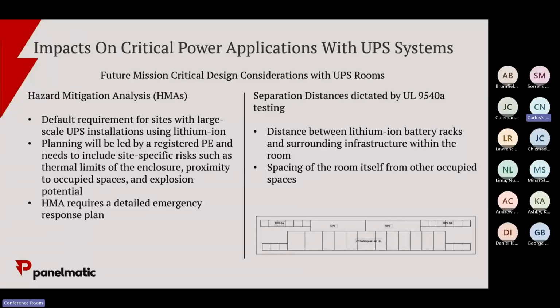The battery manufacturer will probably say you voided our warranty. A lot of the 3 foot spacing from the back is to move it away from the doors in case you have to open them, but it's also against that firewall and against anything else. If you move this into one side of the enclosure, you have basically a 2-hour rated firewall that separates the gear, electrical equipment, or whatever else is in the room from the batteries, and then you have 3 foot of clearance from that.